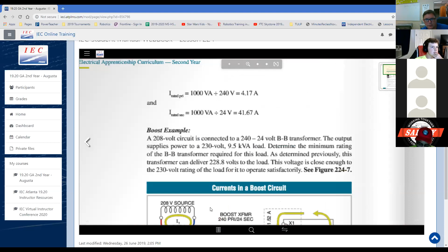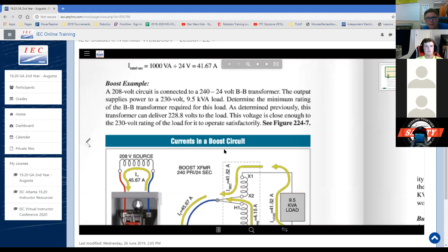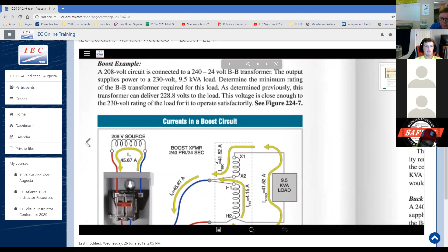All right, so let's look at an example. And this is page, what page are we on? We're on page 224-6 in the book. All right, a 208 volt circuit is connected to a 240 by 24 volt buck boost transformer. The output supplies power to the 230 volt 9.5 kVA load. Determine the minimum rating of the buck boost transformer required for this load. As determined previously, this transformer can deliver 228 volts. We got the 20.8 volts added to the 208 earlier. This voltage is close enough to the 230 volt rating of the load for it to operate satisfactorily.